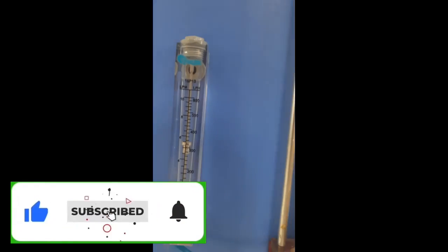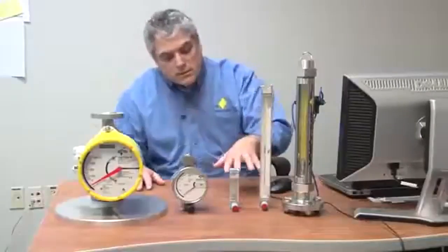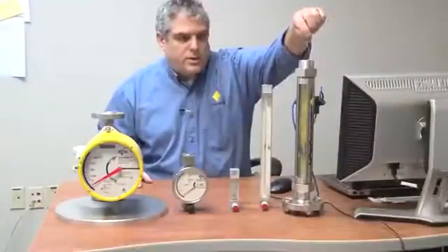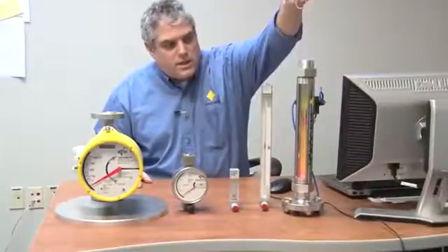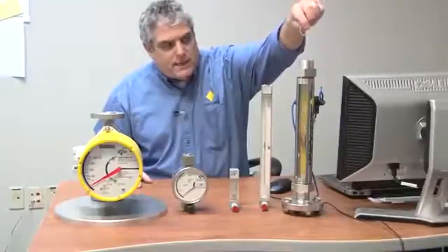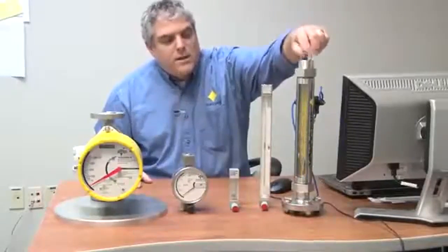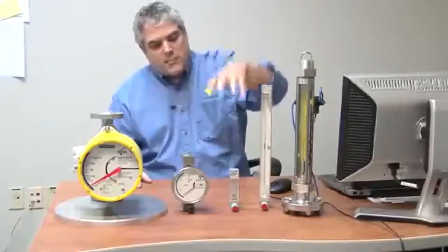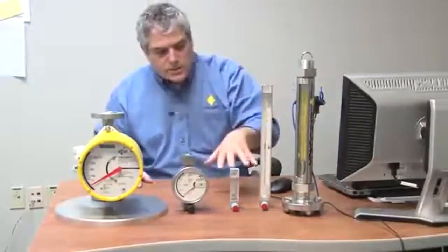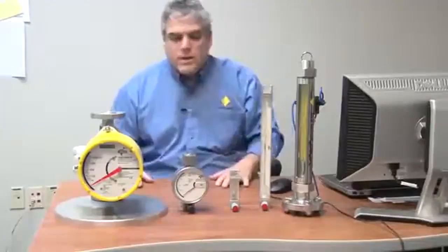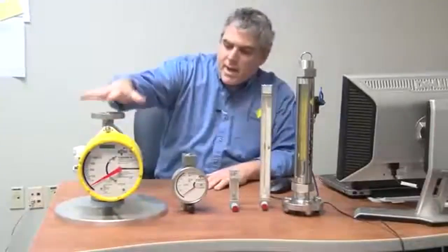It's a variable area meter where the pressure drop is constant, but with change in the volumetric flow rate, there is change in the cross section area through which the fluid is flowing. And other than these flow meters which we have shown you, the rotameters, there are other examples of different sizes. Apart from that, you can even attach a scale, like a clock type can be made. So calibration is done such that with small changes we will have more deflections. That way, full bore meters of this type are also there.